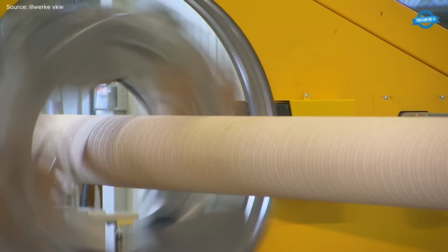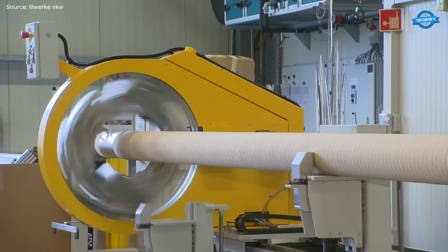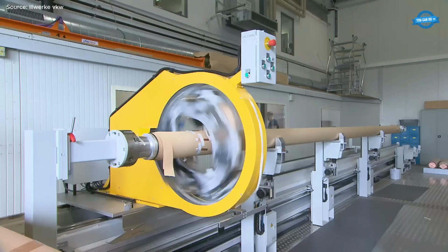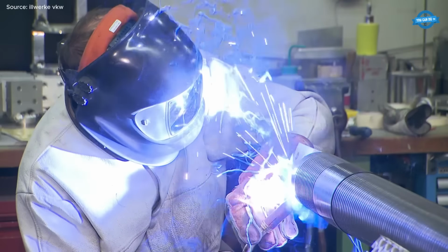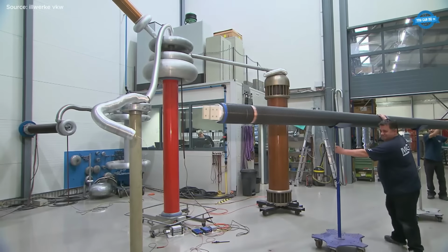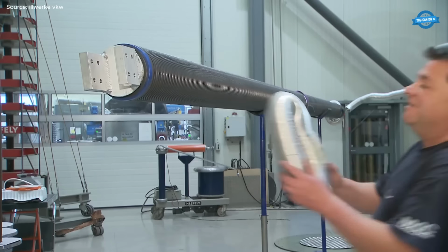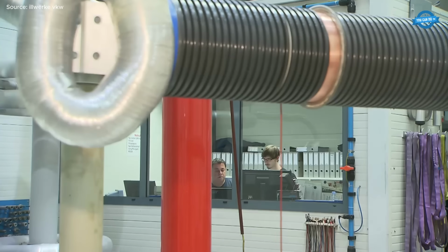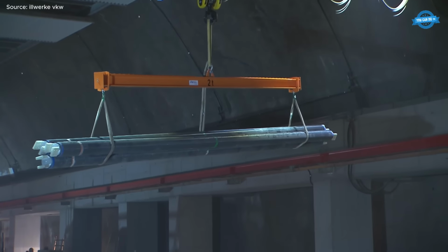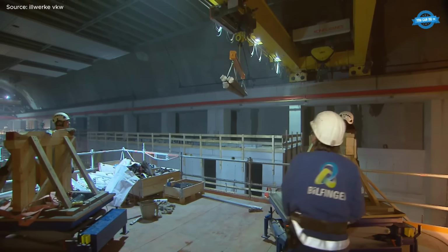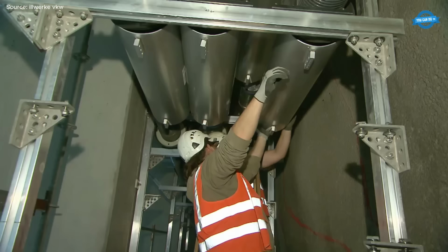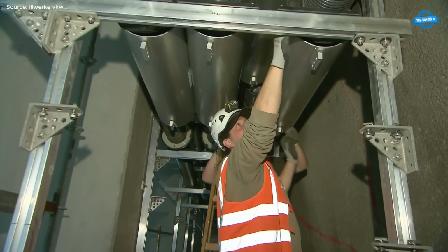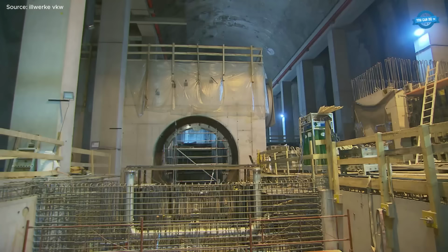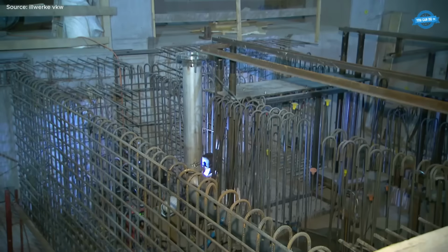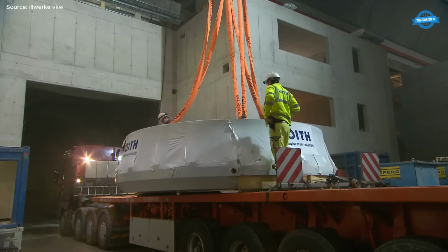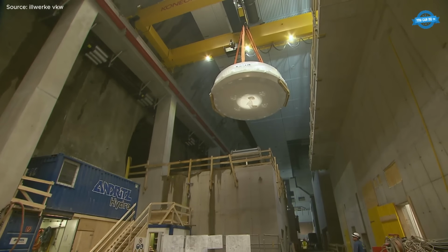Inside the cavern, the assembly of the first machine set is moving at high speed. The upper half of the stator, weighing 112 tons, is lowered onto the lower half. The rotor, with its 14 magnetic poles, each weighing 7 tons, is inserted with a tolerance of just 1 millimeter. This requires fingertip feel from the crane operators, as the total weight exceeds the capacity of a single crane, necessitating a tandem lift using both hall cranes.